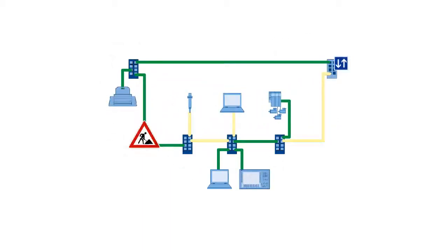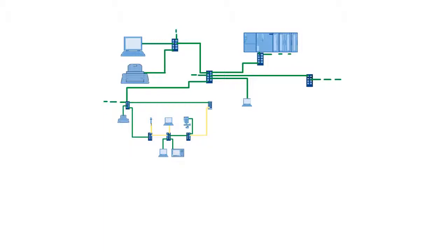The functioning of the network is restored by these measures. With the exception of the failed components, all nodes can now communicate again with each other without any disruption. After the fault has been removed, the redundancy manager restores the original configuration. The ring, which is monitored via high-speed redundancy, may also be part of a larger network.